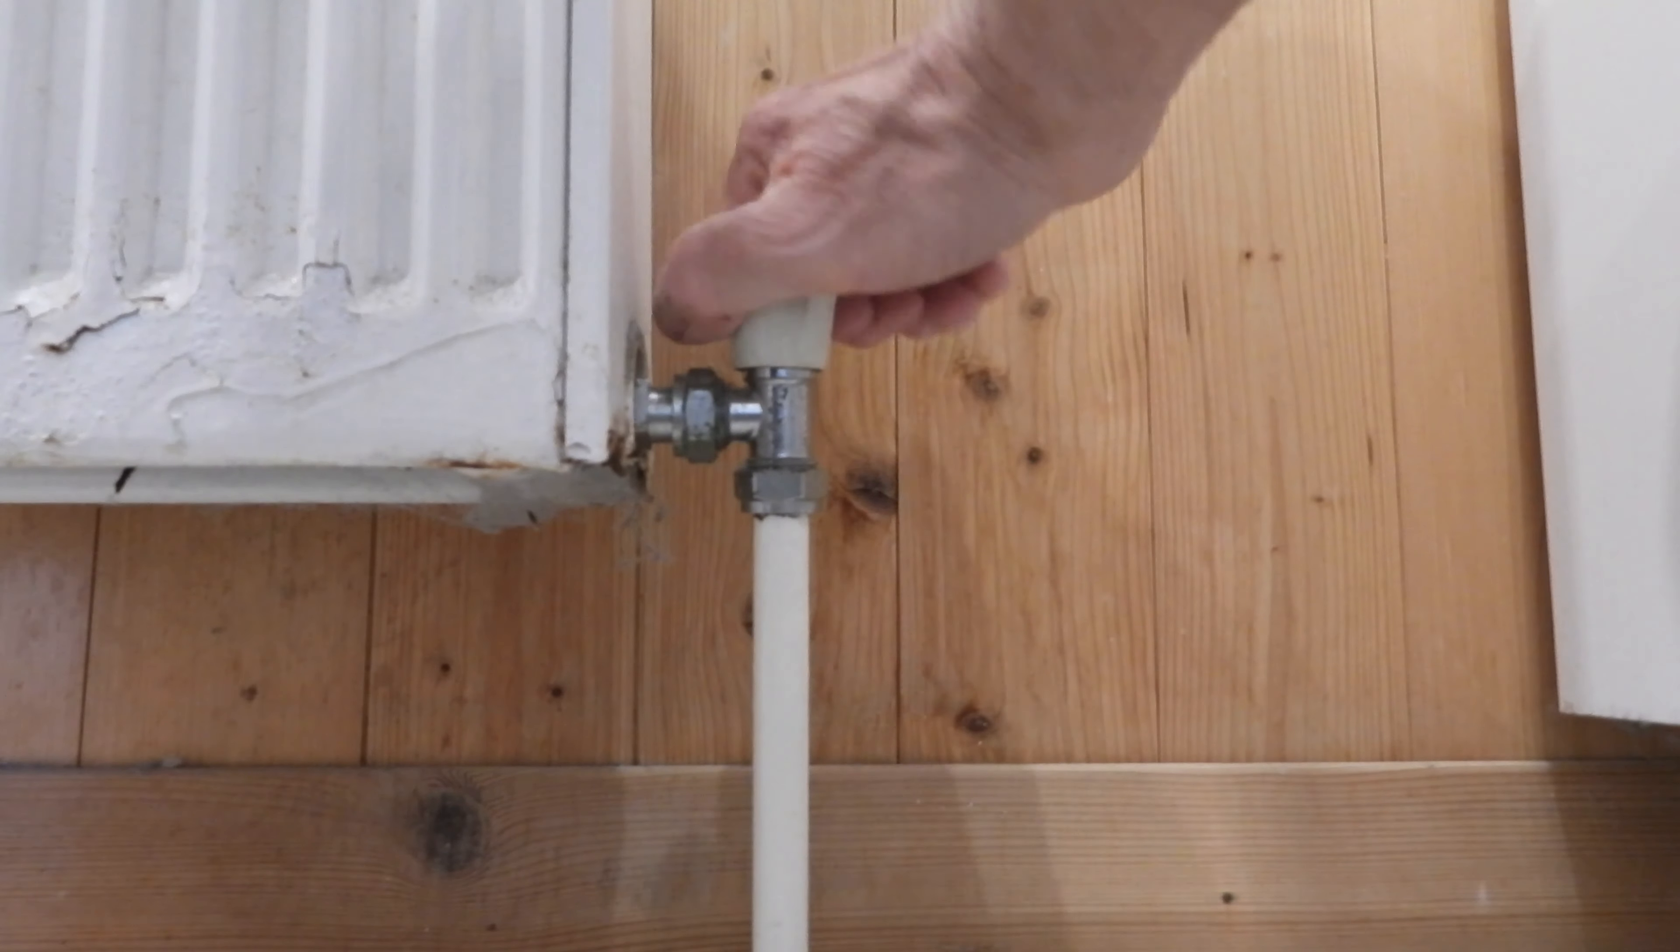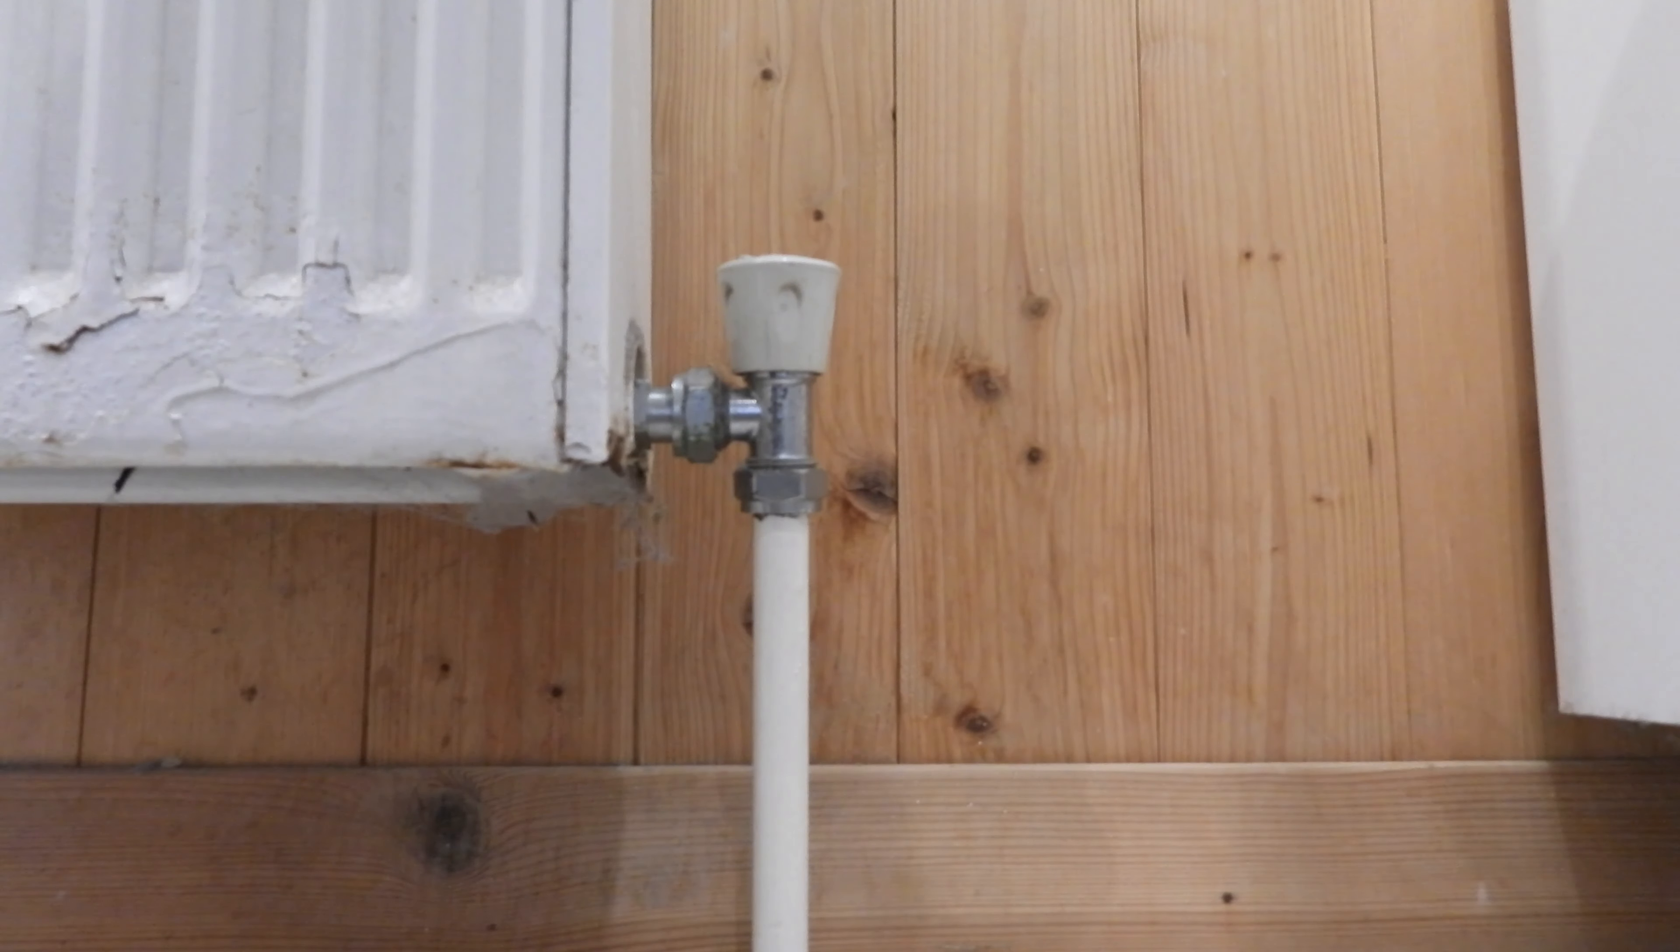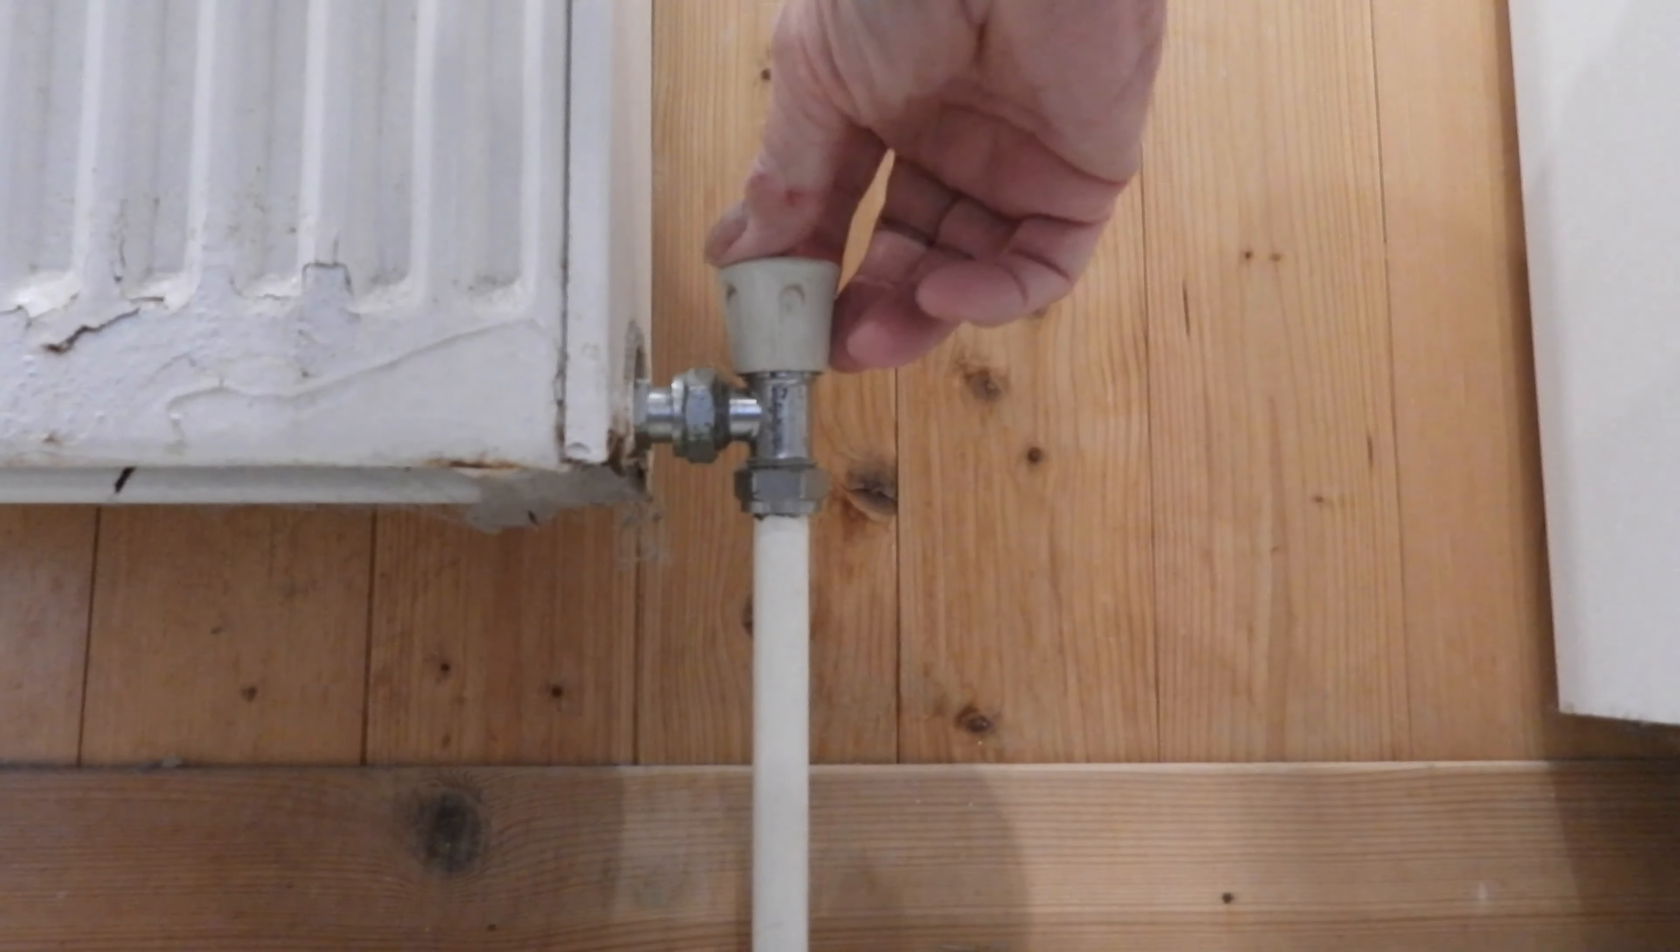Sometimes it's so stiff you might think you're there and it's not quite there, but when it's there it's really tough and that is off. The rad should go off. If it doesn't go off when this is turned right down like that, then once again there's a fault in the valve.